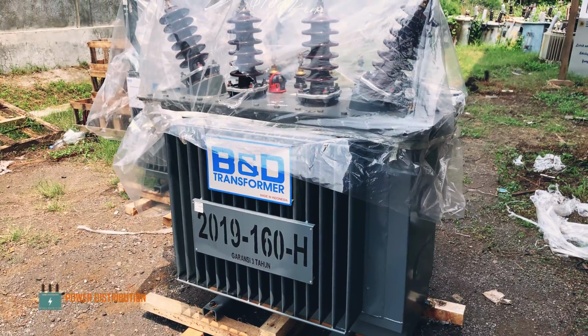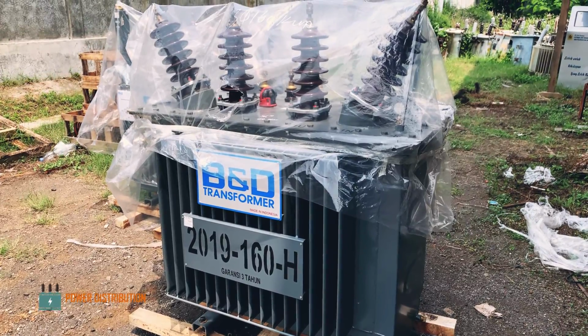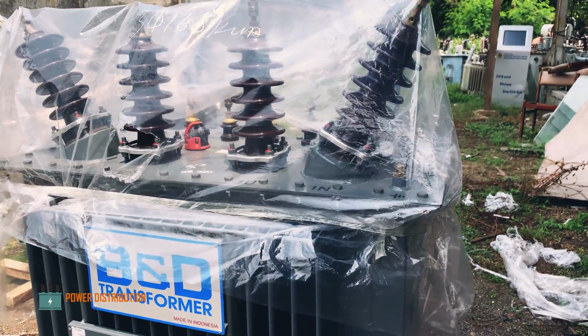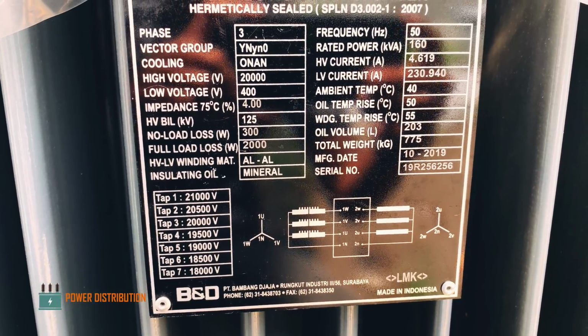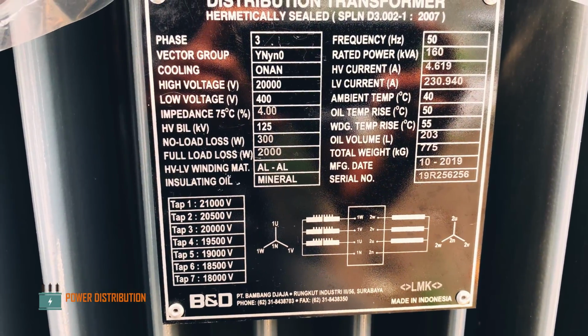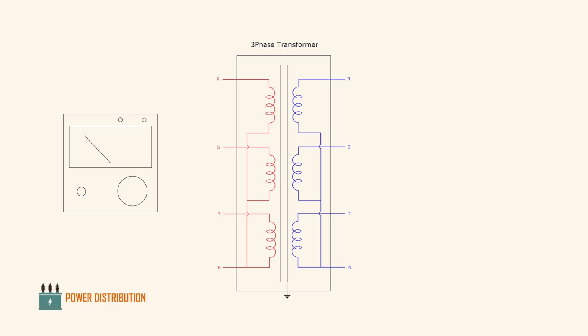Before we do an insulation test on this transformer, it is very important to check the wiring or the vector of this particular transformer. As you can see, this transformer has a Wye-Wye connection. So in this particular case, all the three primary terminals plus the neutral will act as a short circuit. The same condition also applies to the secondary windings, which is all the three terminals plus neutral will act as a short circuit.